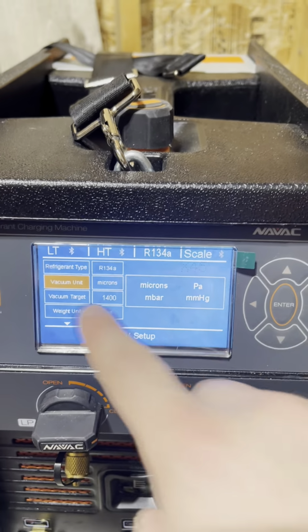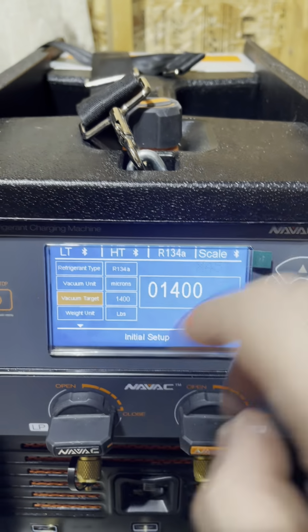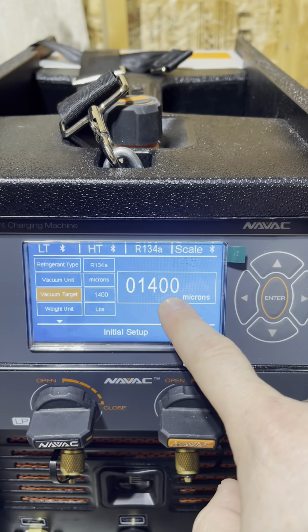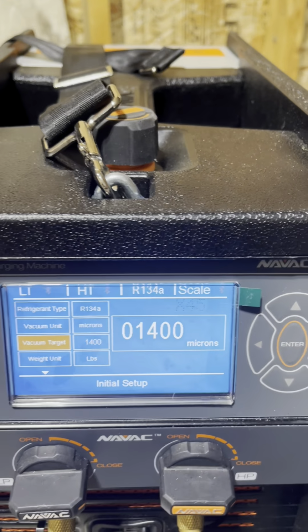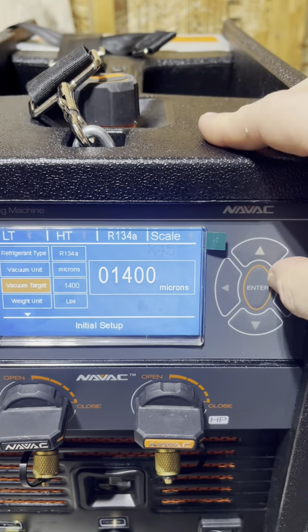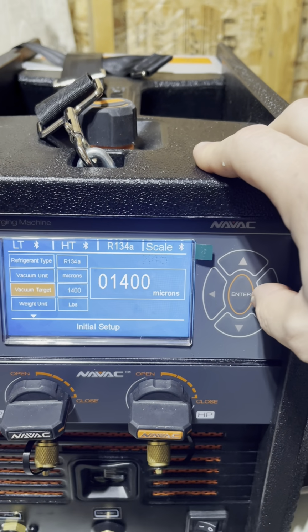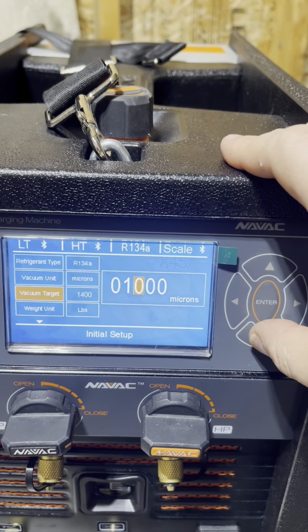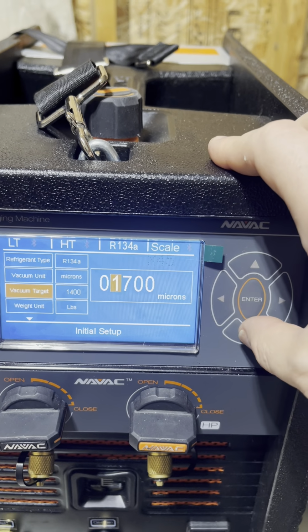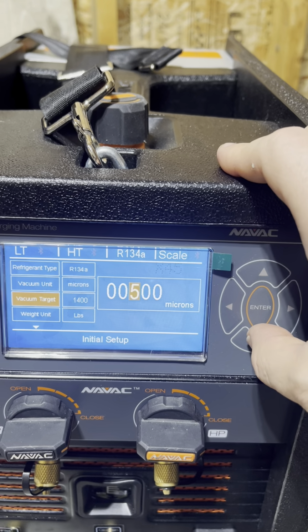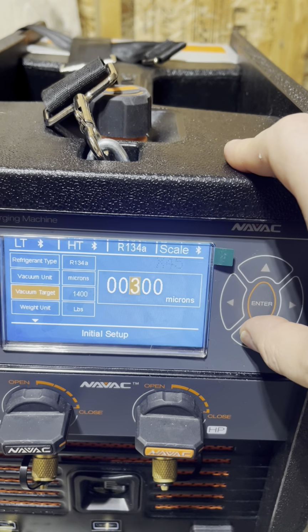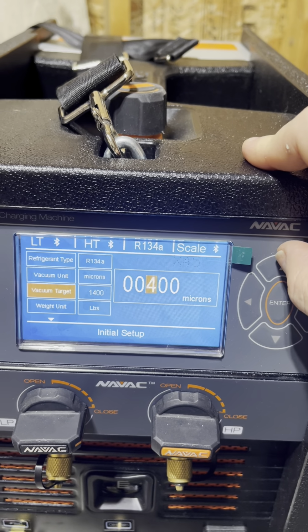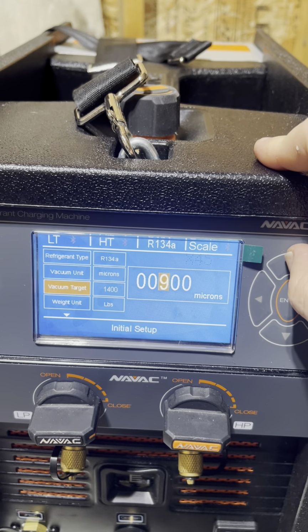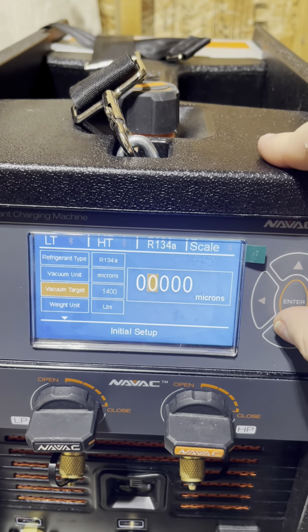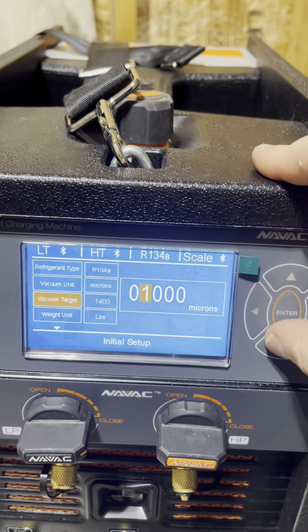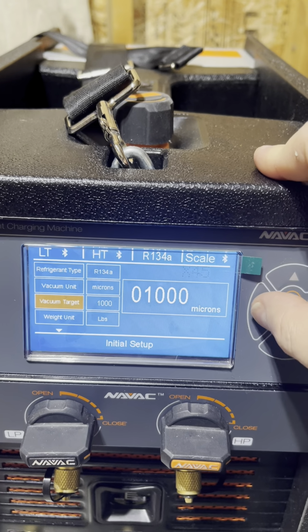Then you're going to go to the next step, which is your vacuum target. I usually keep it at 1400. You can keep it higher or lower as you wish, but you can change it to either 500 microns, or you can even go down to 100 microns, so it's up to you. For me, I usually use about 1000 microns to 1400 microns for my systems. That works good.